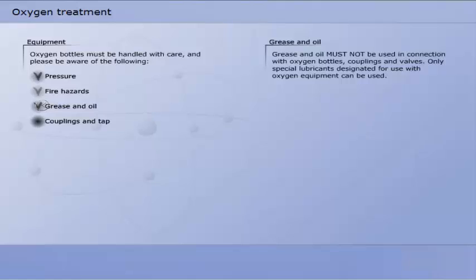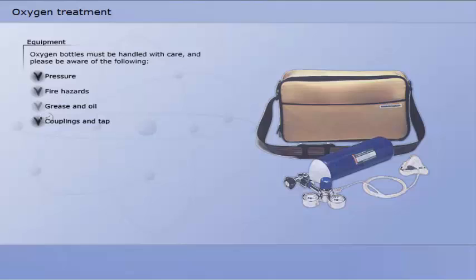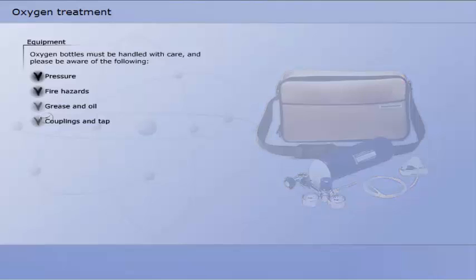Grease and oil must not be used in connection with oxygen bottles, couplings and valves. Only special lubricants designated for use with oxygen equipment can be used.